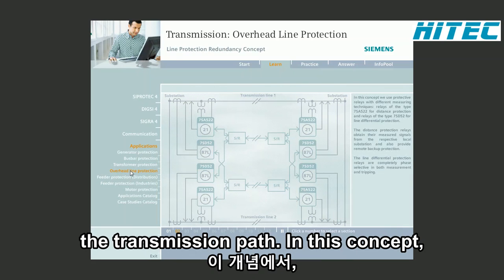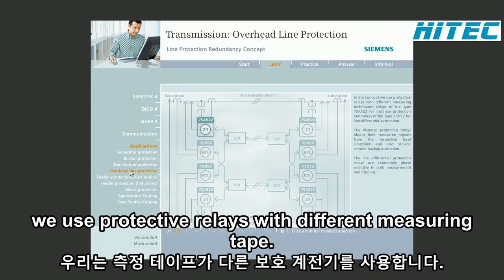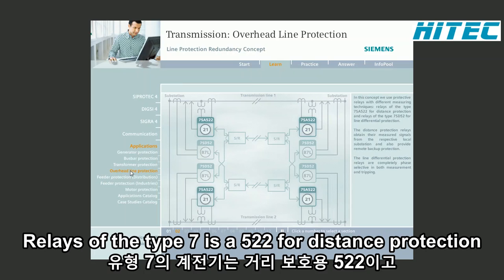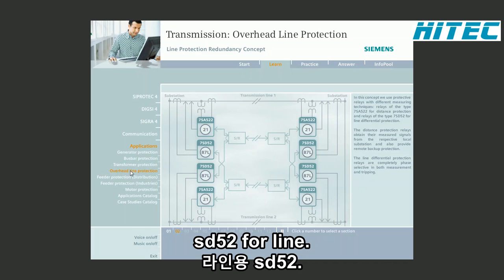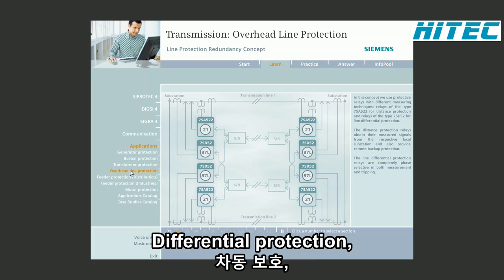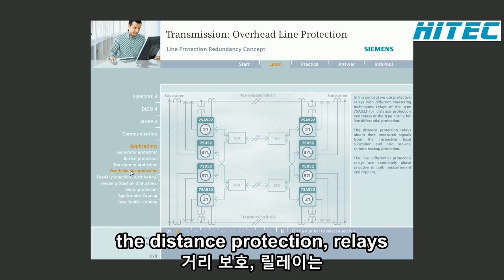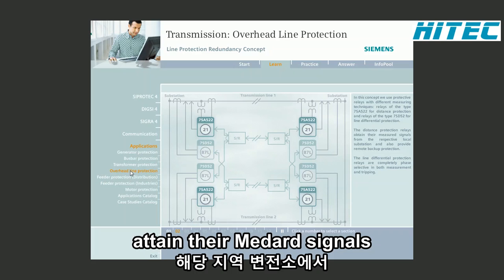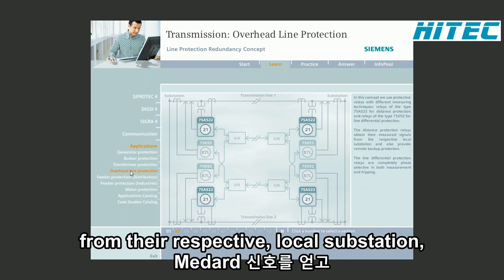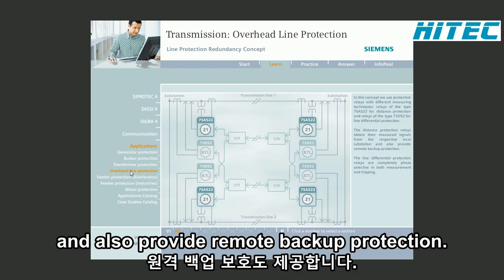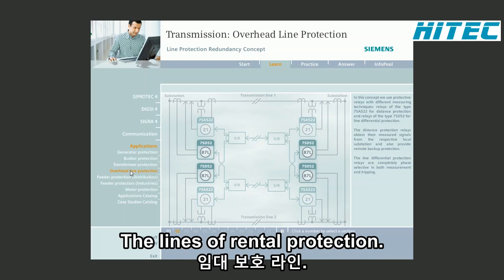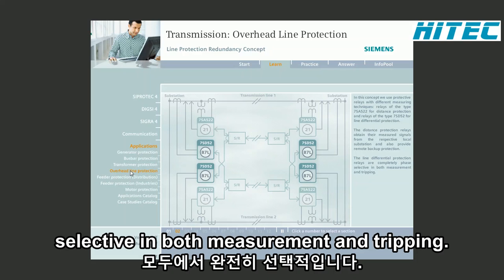In this concept, we use protective relays with different measuring techniques. Relays of the type 7SA522 for distance protection, and relays of the type 7SD52 for line differential protection. The distance protection relays obtain their measured signals from the respective local substation and also provide remote backup protection. The line differential protection relays are completely phase selective in both measurement and tripping.